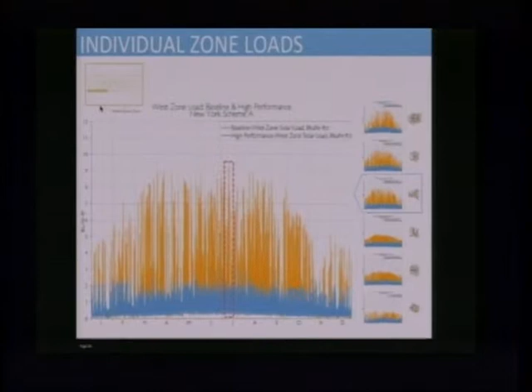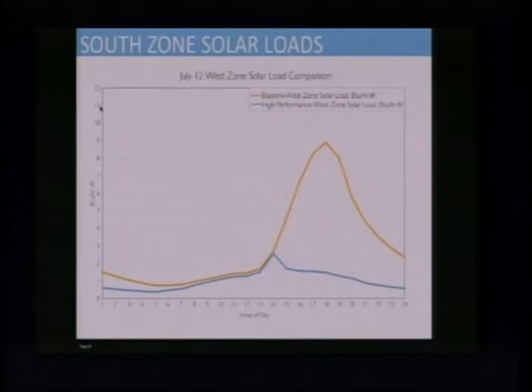Question: how does it compare to the other loads—is it the most significant in terms of cooling? That's a good question—yes, as far as cooling, definitely. We don't have people, lights, or equipment on this graph, but solar load trumps all of that for sure. That's why it's important to lop this off, since there are other loads too. This blue line is just the solar load, so it's actually higher, and those radiant cooling panels aren't going to accommodate much more than 6 BTU per hour per square foot.